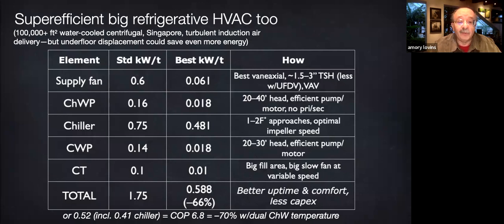Now here, Mr. Lee used some British variable speed vane axial fans and typically German pumps, no primary secondary pumping, which is a sign of excessive piping friction. So these improvements together would cut the fluid handling parasitic loads by an order of magnitude. Notice the 0.6 supply fan versus 0.06, and similarly below.